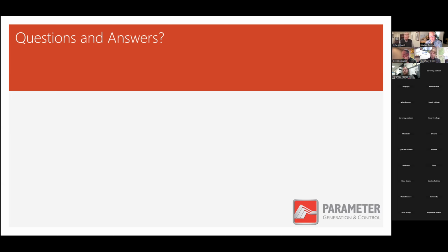But we have fairly well written operations manuals that include the troubleshooting sections. Those are always very helpful to keep on hand and readily available. I find that they are often overlooked or lost fairly easily. So just knowing where your operations manual is and being able to provide that to a contractor is incredibly valuable.